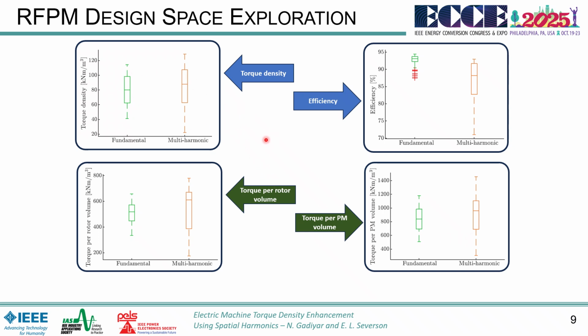Similarly, here are the plots for torque density, efficiency, and other performance parameters, which is torque per rotor volume and torque per PM volume. You can see that the torque density on an average is significantly higher for the multi-harmonic designs. Similarly, the efficiency, although lower, is due to the iron losses which come in when you have harmonics. And then you can look at the torque per rotor volume, which is higher, and torque per permanent magnet volume.